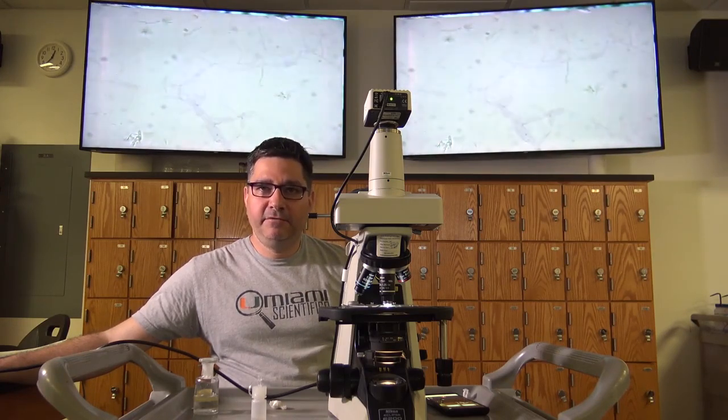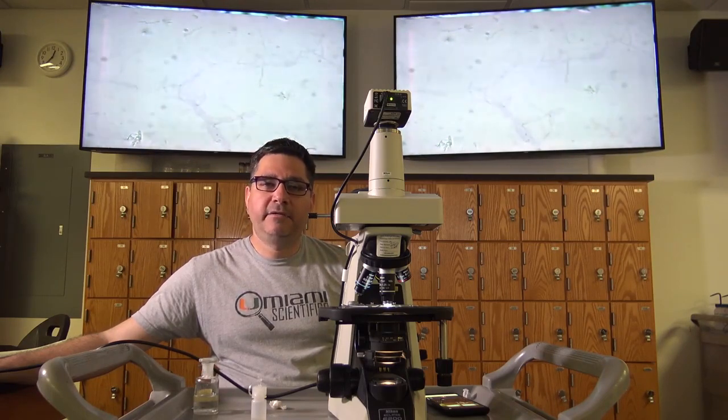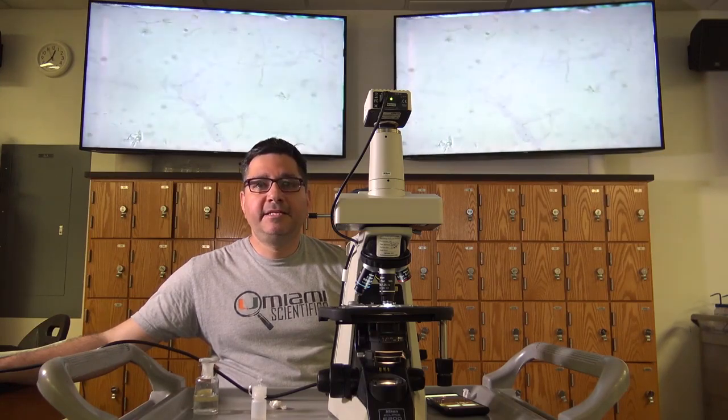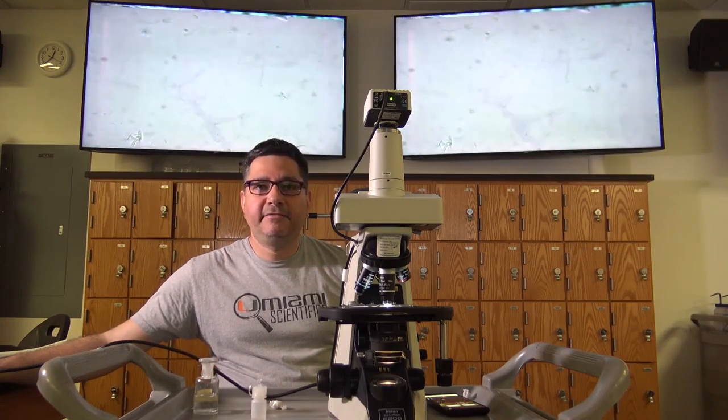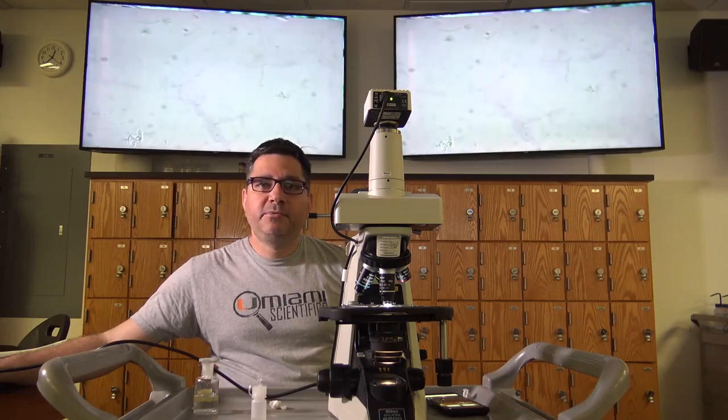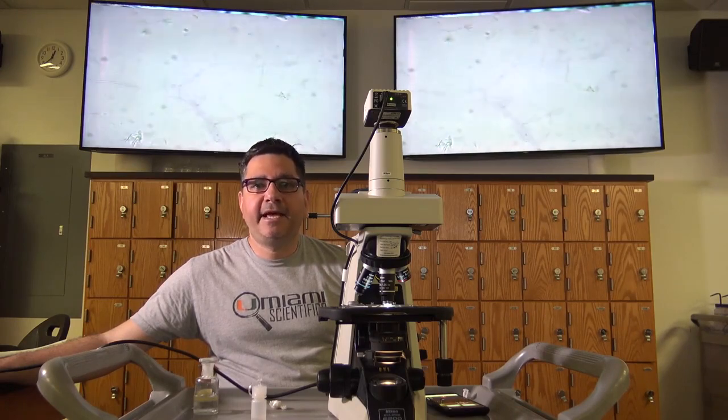If you lose the specimen at 100x with the oil, do not go back to the 40x. Instead, go directly to 4x, fine focus, then to 10x, fine focus, and instead of going to the 40x, you would rotate the objectives in the opposite direction and refocus using the 100x objective. By doing it this way, you do not place any of the objectives in contact with the oil except for the oil immersion objective. If this does not solve your problem, check to make sure that your slide is not upside down.